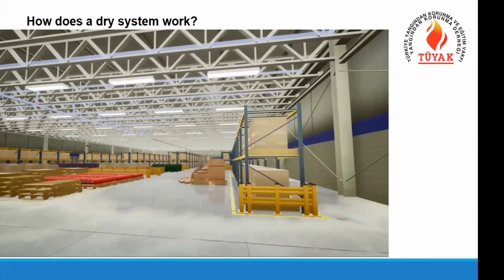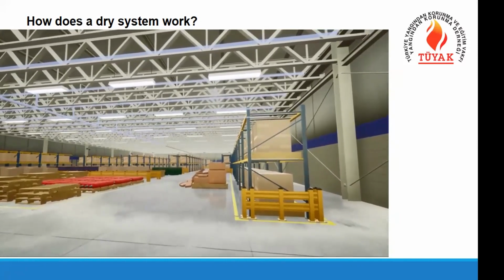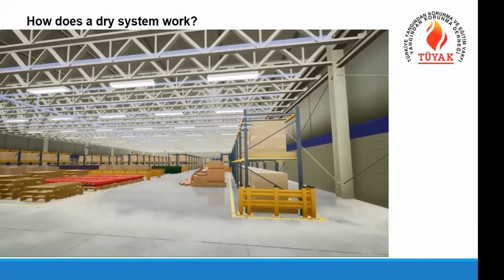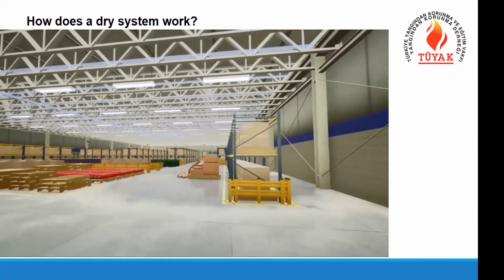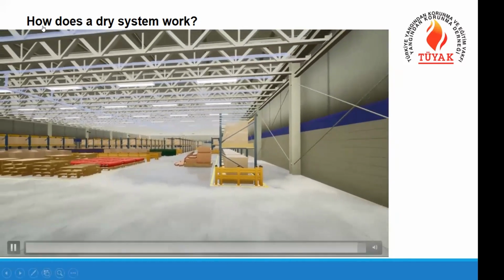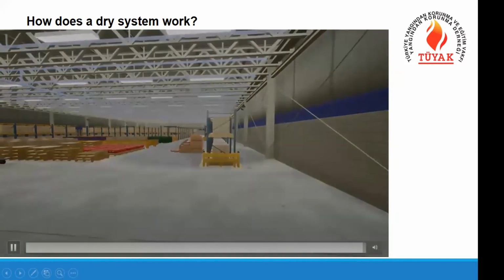So normally before the activation of the system, we don't have any water inside the pipes. So this is called a dry system and dry alarm valve. And it's again giving an alarm, like a mechanical alarm and an electrical alarm, that the system operated, and it gives information about the system operation.